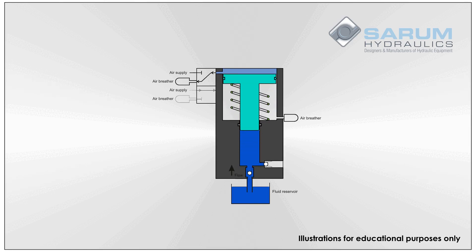A compressed air line in most installations only go up to around 7 bar of air pressure. If the pistons were the same size, that would result in only 7 bar of hydraulic pressure on the piston below. By making the hydraulic piston area smaller in relation to the air piston, you achieve a pressure ratio.